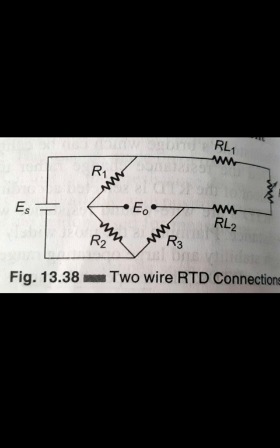The 2-lead RTD is lower in cost and normally used where the lead resistance is low compared with the ohms per degree centigrade resistance change in the RTD, or when wire resistance compensation is provided in the instrumentation.